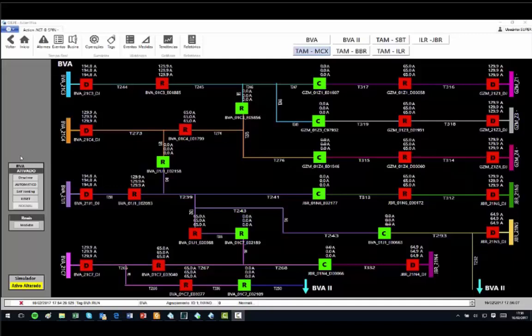This application was implemented in two distribution utilities and controls more than 150 devices in one of them, where most equipment are pole reclosers or switches.